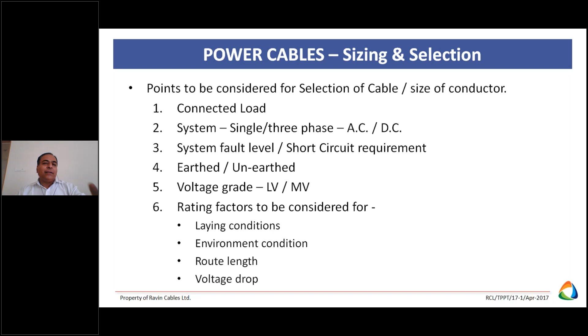Why is it route length? Because of voltage drop. Suppose here we are feeding 440 volt at the sending end; at the receiving end it should ideally be 440, but due to the resistance of the conductor, voltage drop is there, and voltage drop depends on resistance. Resistance means one is the conductor cross section, and secondly the length of the conductor. As length increases, conductor resistance increases, so voltage drop increases. So these are the basic requirements for the selection of the cable.